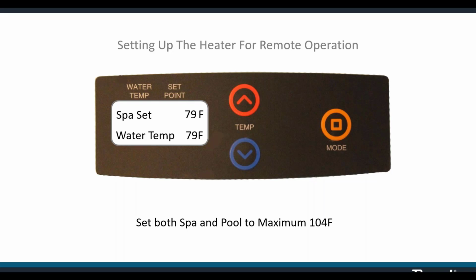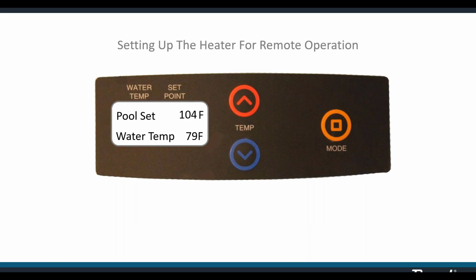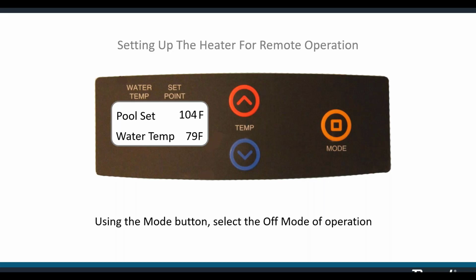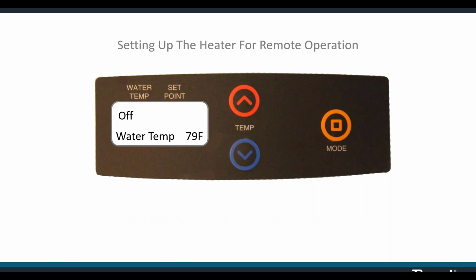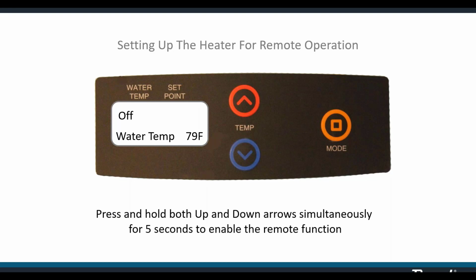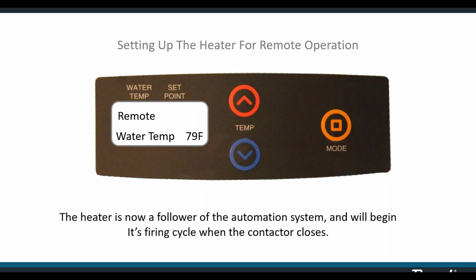Now we need to tell the heater to pay attention to the automation system. So first we'll set the temperatures for the pool and the spa all the way up to 104. This fully enables the heater so that it doesn't get in the way of the remote. All right. Now using the mode button, we will select the off mode of operation. Then press and hold both the up and down arrows simultaneously for 5 seconds to enable the remote function. The heater is now a follower of the automation system, and it will begin its firing cycle when that contactor closes.